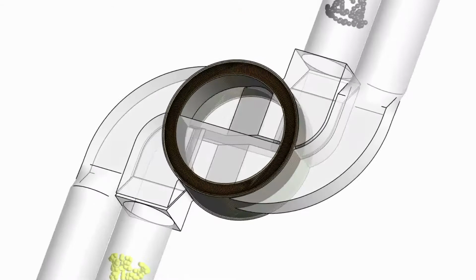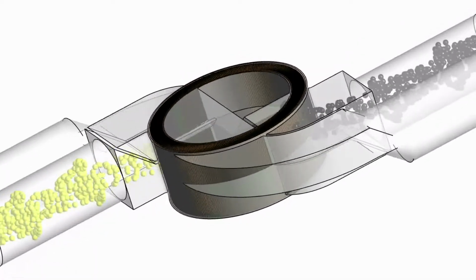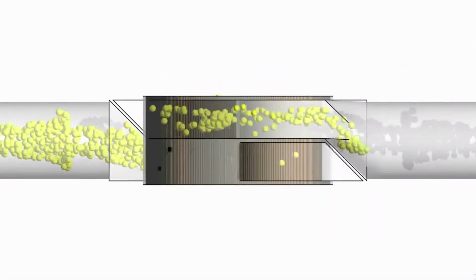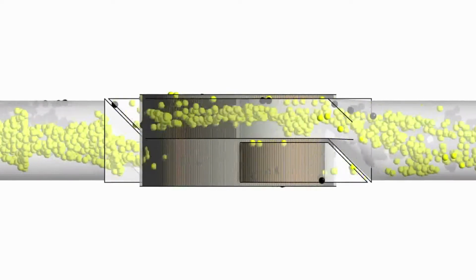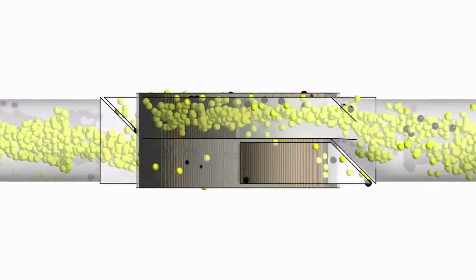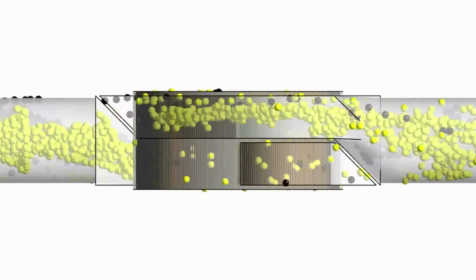The characteristic property of this so-called counterflow heat recovery fan is that only one crossflow fan generates both airflows at the same time, and the fan blades work as regenerative heat exchangers simultaneously. Both airflows pass through the fan blades symmetrically, but at different levels, perform a level change inside the fan and are blown out again through the fan blades.